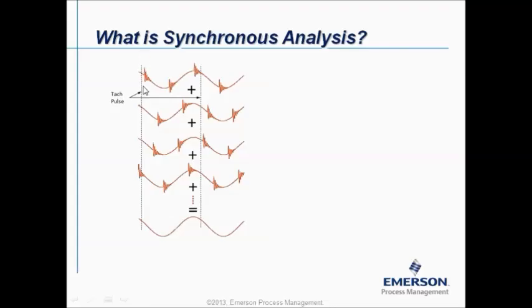Now, the starting point of the waveform of the snapshot is more or less random. But in synchronous analysis this is different. The starting moment of the snapshot is always at the moment that the tach pulse is coming in. So, it is always on the same position of the shaft. And instead of doing averaging on the spectra, we will do averaging on the waveform.